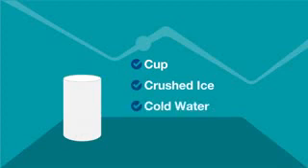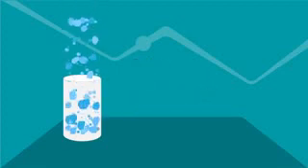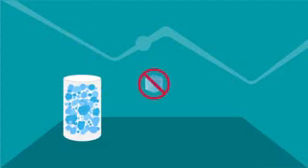Before you begin, make an ice bath using a cup, crushed ice, and cold water. Filling the cup to the top with crushed ice is important for achieving a stable temperature. Cubed ice is not recommended since it will cause higher temperature readings.